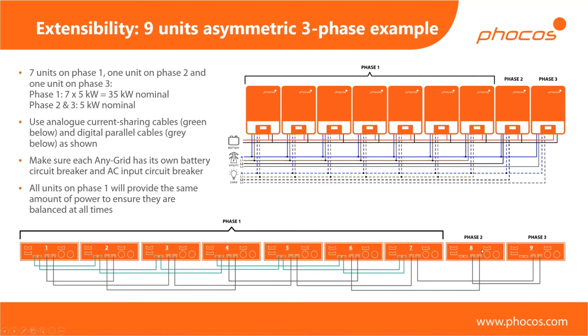And then what you might notice is on phase 2 and phase 3, we have no green cables, because like I said before, you only need the green cables if you have more than 1 unit per phase. On phase 2, we have just 1 unit, and the same thing goes for phase 3.